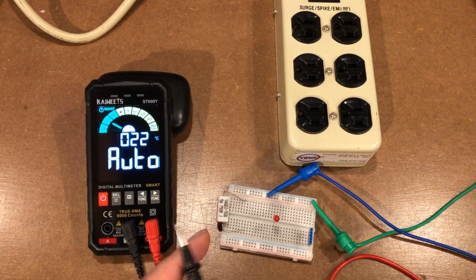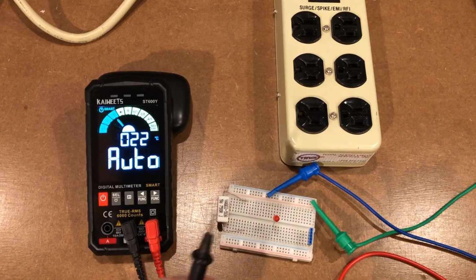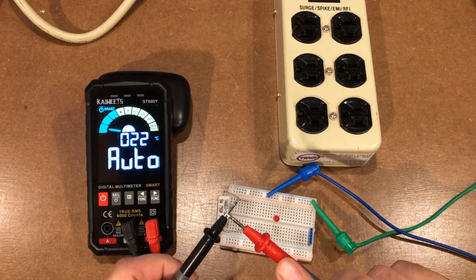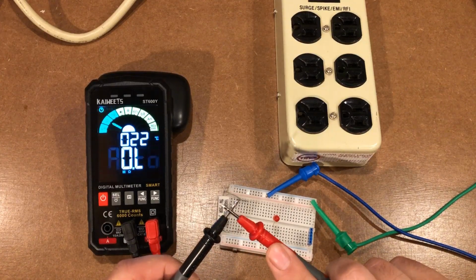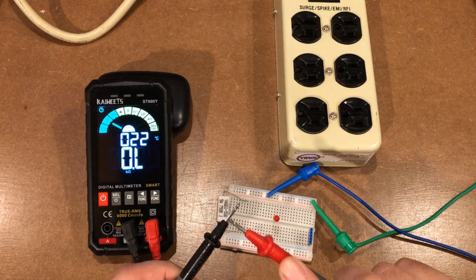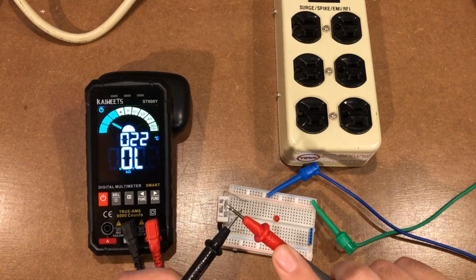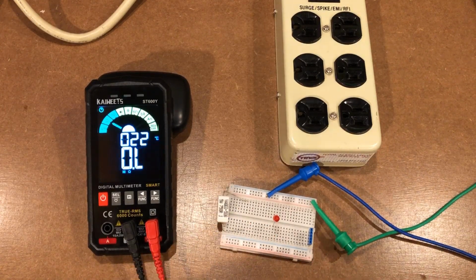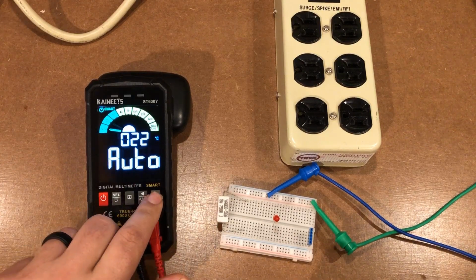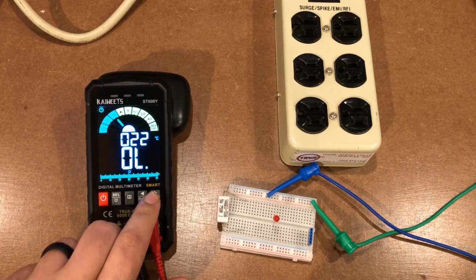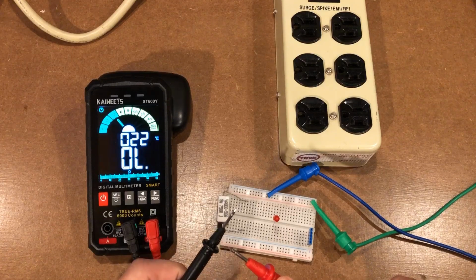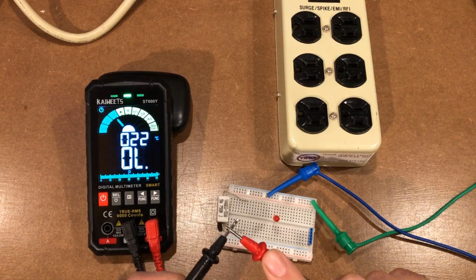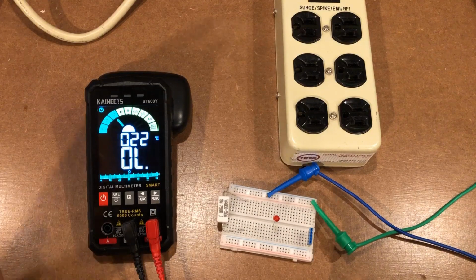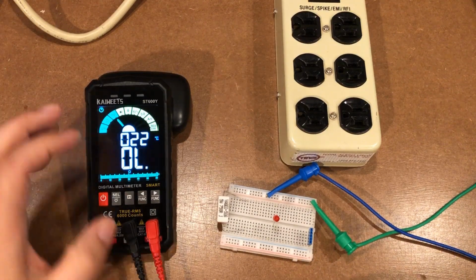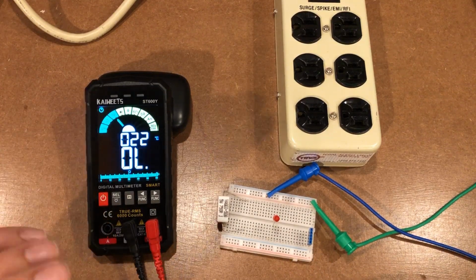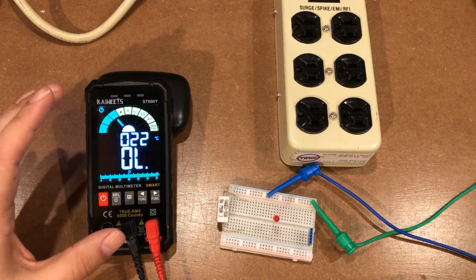I think the easiest way to demonstrate the speed difference is to put it in continuity mode. If I come here in smart mode and do continuity, it will measure. The second time you do it, it's a little faster. The third time is even faster than that, because it's smart, realizing what you're trying to accomplish. But if you put it in manual continuity mode, it's instantaneous. What's neat about the smart features is you can use them, or they're smart enough to get out of your way, which a lot of multimeters don't have.